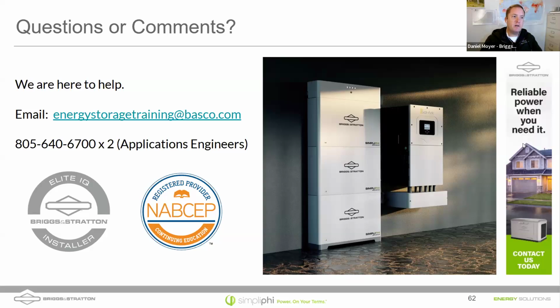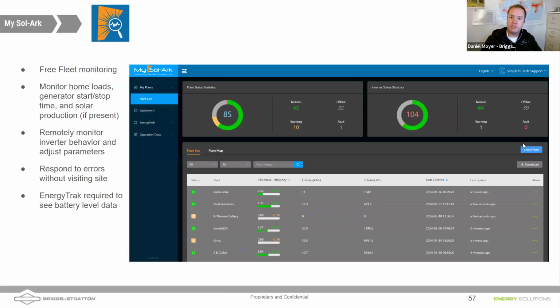Timothy's asking, can AC coupled PV go to a sub panel with loads that's connected to either the load or the gen port? Yes, absolutely, they can. And typically, as I said earlier in the talk, it's a little bit of extra work to reroute your AC coupled solar. So people will just leave the AC coupled solar in the load center, and then you have to have that box checked for AC coupled solar on the load side, which is fine. You can do that, but then the gen port is automatically disabled on a Sol-Ark if you do that. And the telemetry, right? You're not necessarily going to know the output of the PV unless you go to the PV app, because the loads in the load center might consume some of the energy being produced by the PV before it has a chance to go back up into the Sol-Ark.